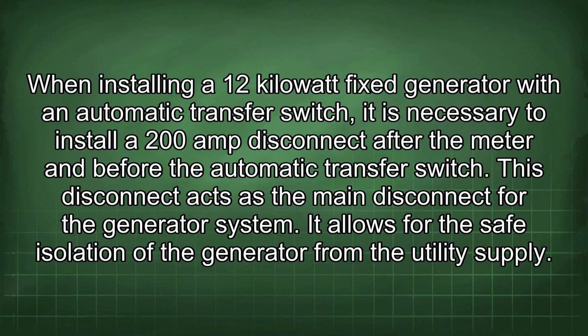When installing a 12 kilowatt fixed generator with an automatic transfer switch, it is necessary to install a 200 amp disconnect after the meter and before the automatic transfer switch. This disconnect acts as the main disconnect for the generator system. It allows for the safe isolation of the generator from the utility supply.